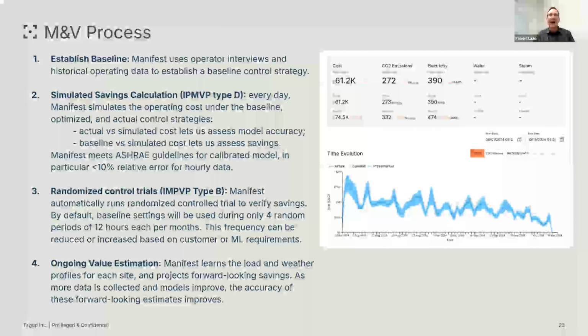Yeah, thanks, great question. Absolutely. I didn't include this here because it would have taken too much time. We're currently piloting adding the chilled water reset to this. The reason it's not done from the get-go is that the closer we get to the air handling unit, the more we expose the system to potentially affecting tenant comfort. We have very strict constraints there. We have a load, and we definitely need to remove that load from the chilled water circuit. We change the condenser set point, and there are no effects on the chilled water side. We monitor that, and there are safeguards in place to never affect the system's ability to cool the AHU and everything downstream. So the closer we go to the other side, the more data we need to monitor what's actually happening in the building.